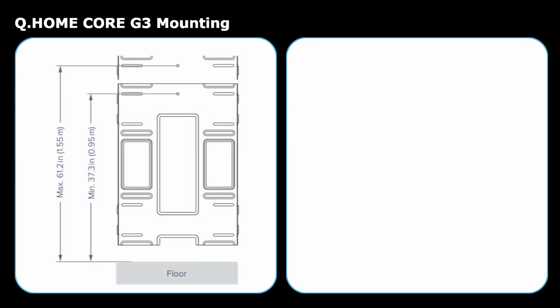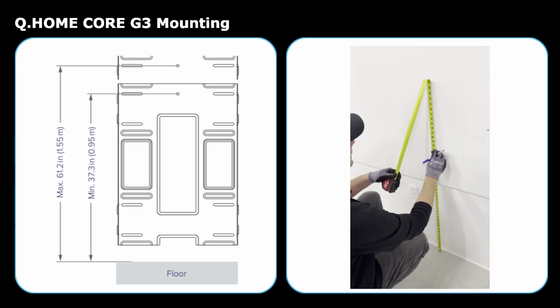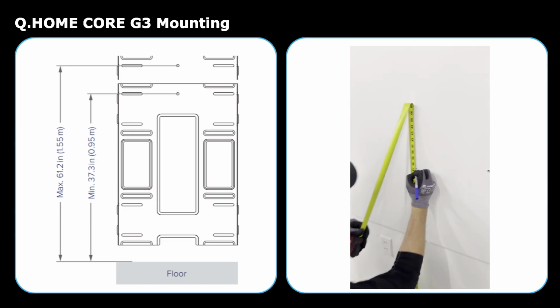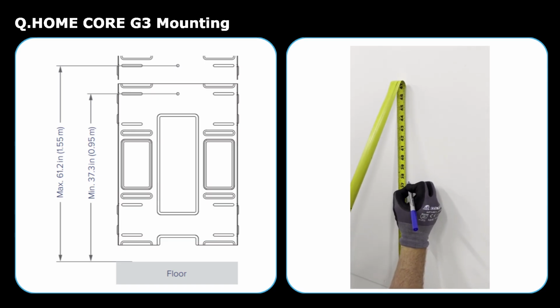When wall mounting, position the top of the bracket about 37.3 inches from the floor and make sure the total installation height does not exceed 61.2 inches. For floor mounting, it is recommended to measure a distance of 37.5 inches from the floor to the center drill hole. For this installation, we will use a height of 38 inches.